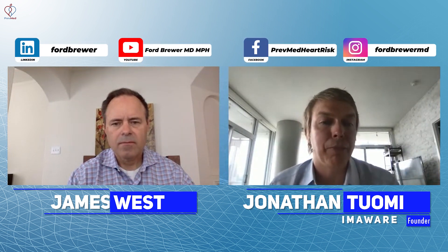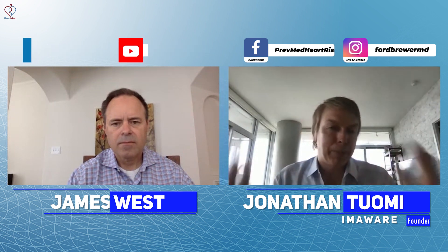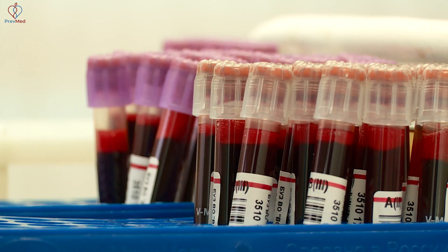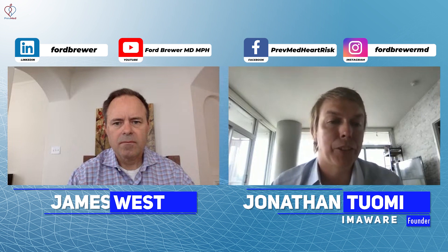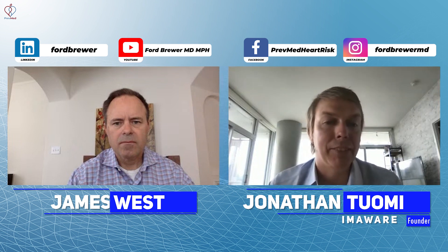The big companies have made investments in technology stacks and lab testing devices that handle larger volumes. They employ lots of people and try to drive pricing down, so they prefer working with larger volumes of blood, and their staff are less specialized in miniaturized testing compared to specialty labs. But you can bring the sample volume from 1/10th of a milliliter down to 1/100th of a milliliter — what's called microliters. Nowadays you can measure blood in just 10 microliters, approximately a drop or a little less than a drop.